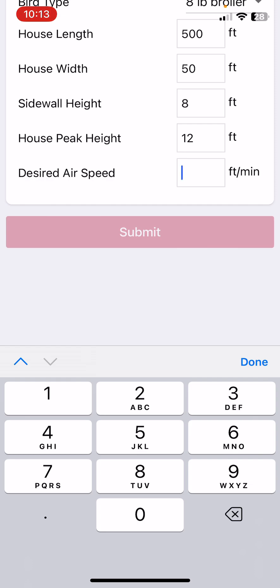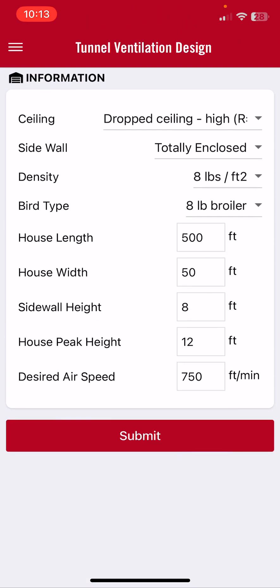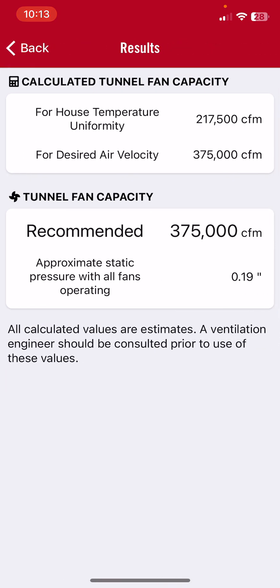The sidewall is eight foot, the peak height is 12, and we feel that we need a minimum air speed of 750 feet per minute. We hit submit. It has now calculated two different tunnel fan capacities. The first is the amount of tunnel fan capacity required to assure no more than a five degree temperature rise — in this case that's about 217,500 CFM. The second tunnel fan capacity is that required to produce the targeted air speed of 750 feet per minute.